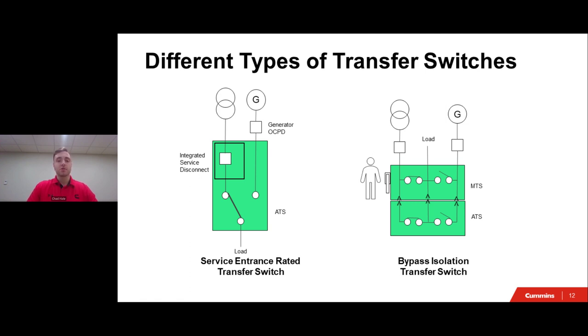What this bypass isolation transfer switch allows is you to separate the automatic transfer switch from the manual transfer switch side of things, but still allow the manual transfer of power between sources and the transfer switch. This is all possible due to a linking mechanism that allows you to isolate the two portions of the switch so that you can pull the automatic mechanism and fix and test whatever is needed within the automatic transfer switch.